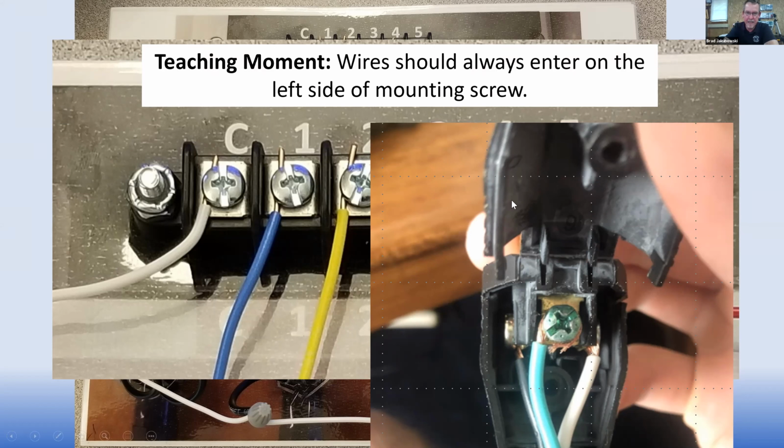Sometimes for simplicity's sake, I don't do a U, or I guess just in these areas here I don't, but it would be very easy for a person to do that. With this right here, you could explain to them that you could either keep it straight or do a U. If you keep it straight, it makes it much easier to remove the wires once you loosen them up. But in a lot of controllers, especially in golf, where you're using like 10 or 12 gauge wire, sometimes it's very difficult to get those wires bent like that and be able to work with them. It makes them very difficult to work with.